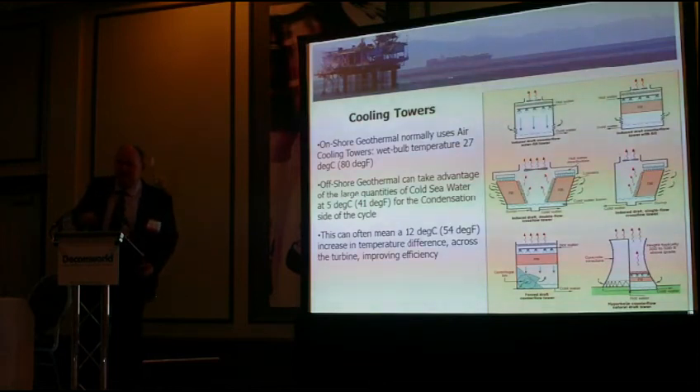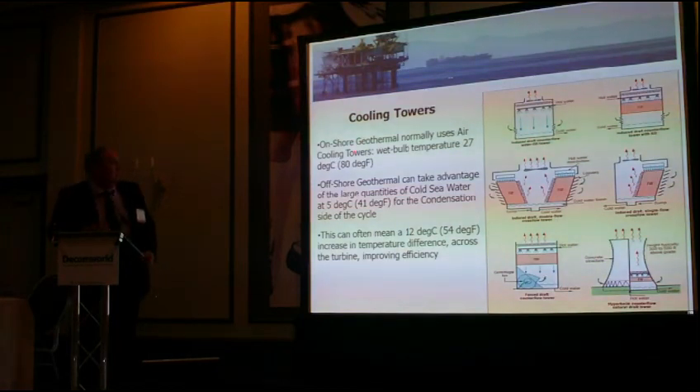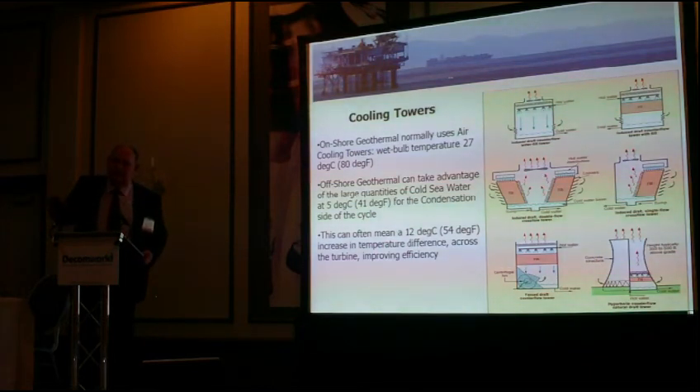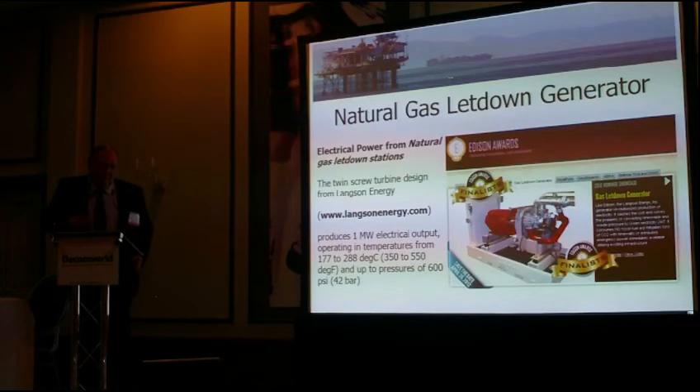Cooling towers is another important point. On land, average air-cooling towers achieve a wet-bulb temperature of about 27 degrees centigrade. In the North Sea, you've got abundant cold water at about 5 degrees centigrade. So you've got a 22-degree difference that can be used with a low boiling point working fluid. You can have the condensate level at a much cooler point and still get the power out.